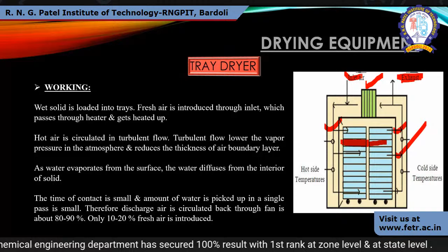So hot air is in turbulent flow, which reduces the thickness of the air boundary layer. As water evaporates from the surface, water diffuses from the interior of the solid. The exhaust takes out the wet air coming out from the right hand side of the tray, and that reduces the moisture content inside the chamber, right? The air does not just pass through once; we recirculate it with the help of a fan mounted on the top. About 80 to 90% of the air is recirculated, and 10 to 20% fresh air is introduced each time, right? So air is continuously circulated inside the dryer, and we keep it for 3 or 4 hours of drying.